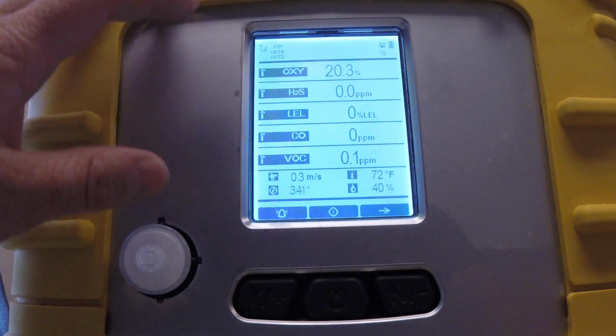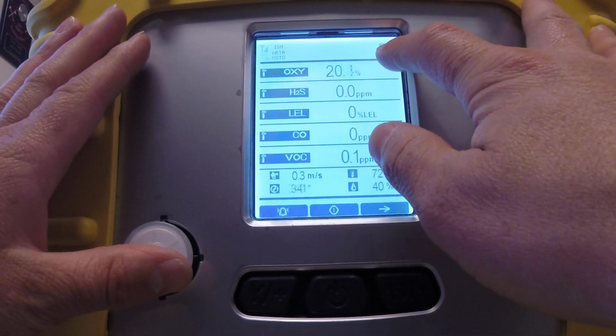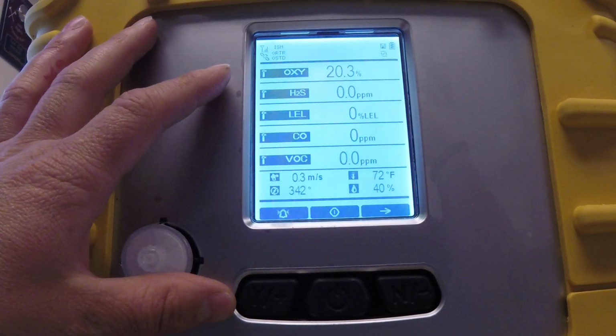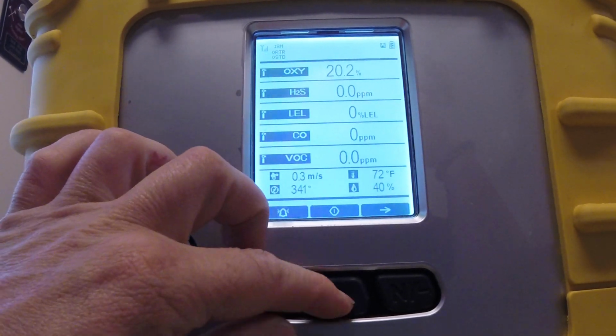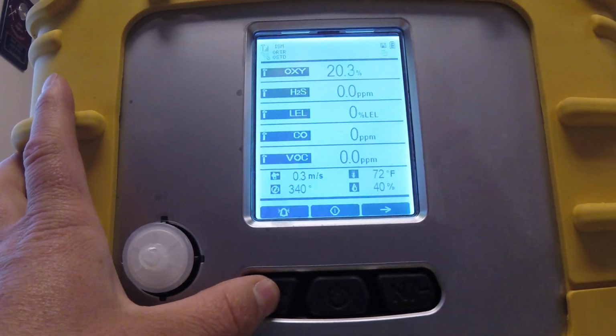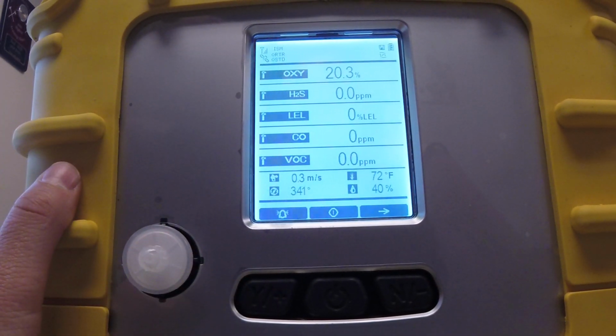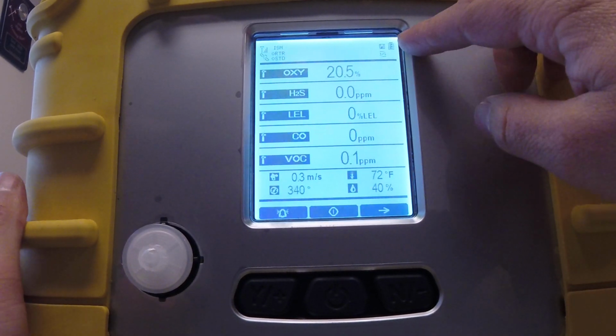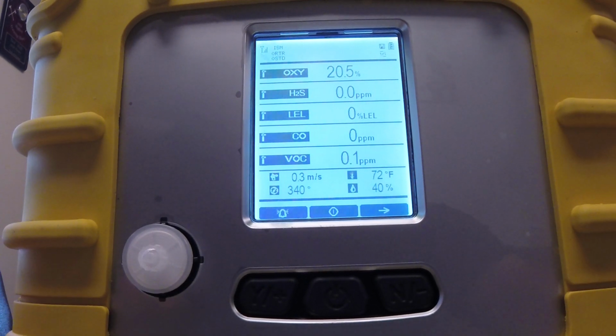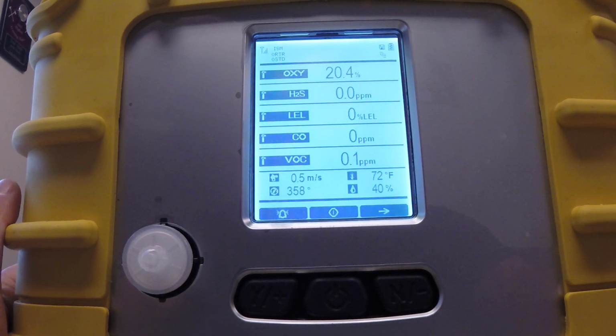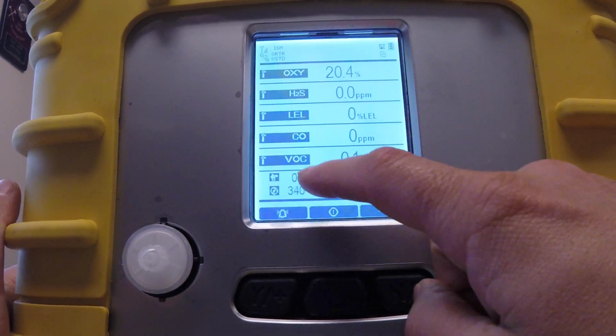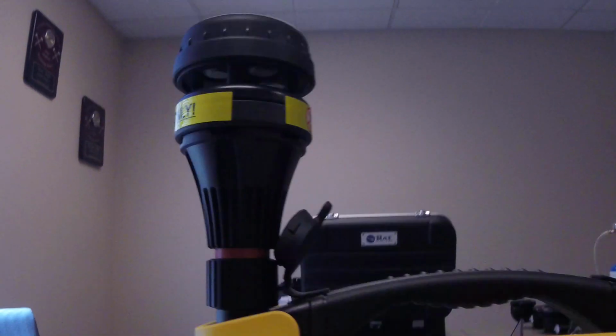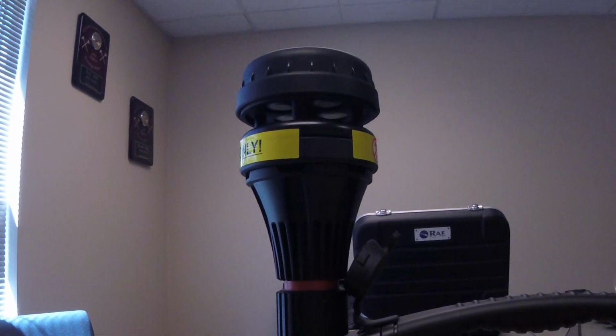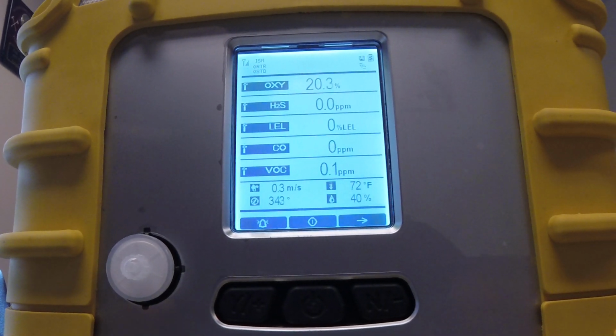So this is a pump icon that's showing that the pump is running. It's data logging and gives us kind of a... alright. So I must have blocked the pump on accident. So what we just have is a typical 5-gas with a weather station. So you can see it's giving us real-time weather readouts. The weather station is that job right there. So be careful with it. It's made of plastic and probably breaks fairly easily. We're not going to test its durability though.